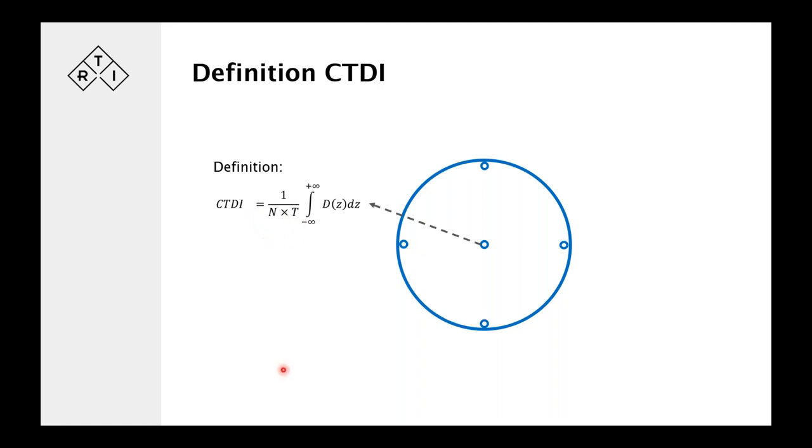So this is the definition of the CT dose index variable. But what happened quite early was that to measure the CTDI in the phantoms, they used ion chambers with an active length of 100 millimeters. That means that anything beyond 100 millimeters, of course, couldn't be measured.